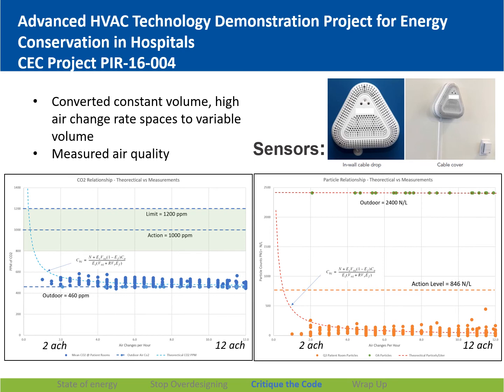We put sensors on the wall and tracked temperature and humidity and VOC and CO2 and particles. We got this huge data set, 73 locations, 6 months worth of data, so 8 million data points. And the charts that you're looking at here are from the patient rooms. You can see air changes per hour on the x-axis and contaminants on the y-axis. A couple amazing things here. This data very quickly debunks the idea that 10 air changes or 12 air changes is better than 2 air changes. That is just not true. You can see the levels are pretty much the same under those airflow regimes.